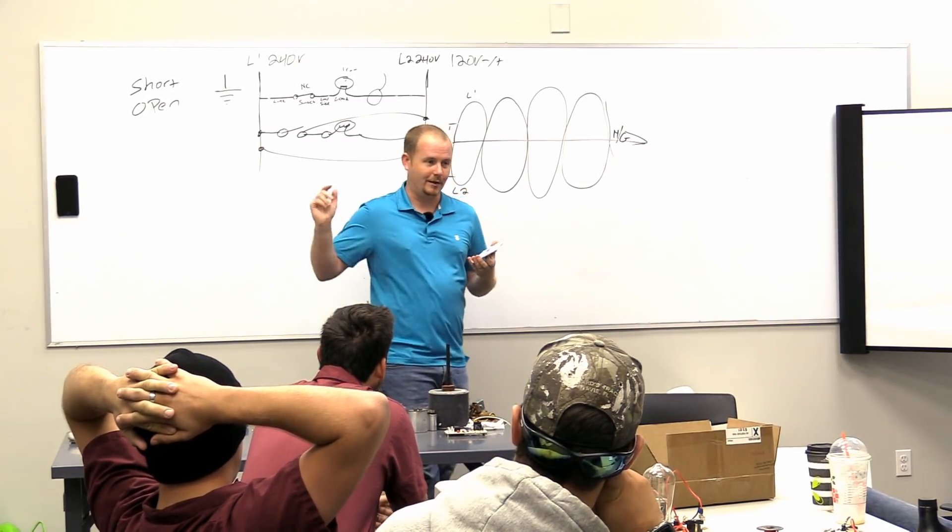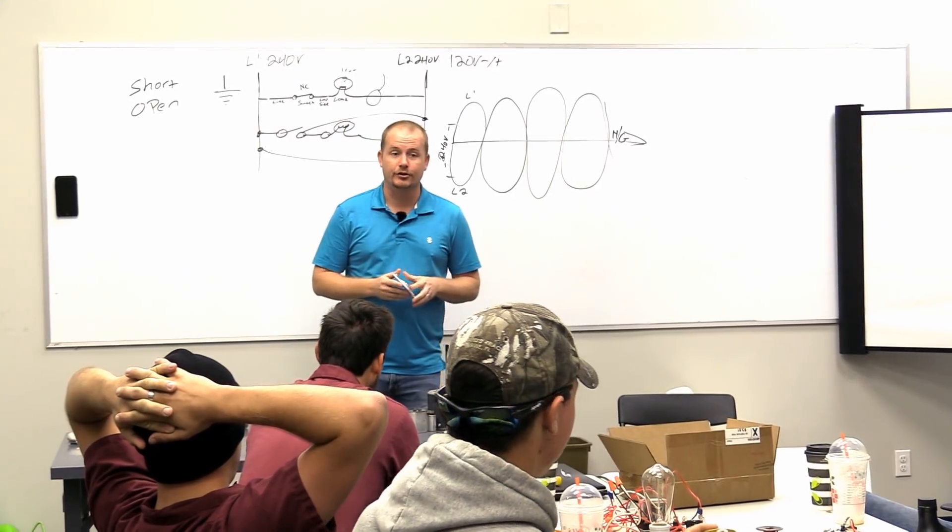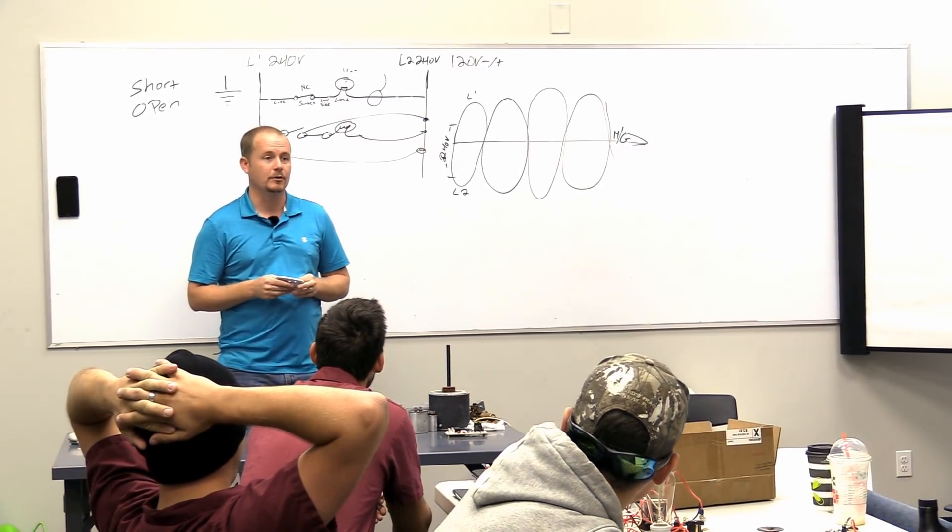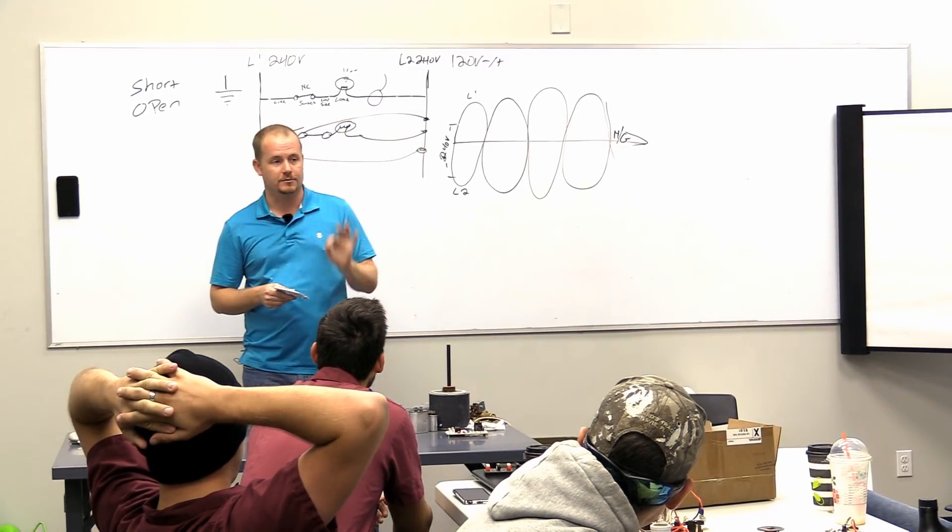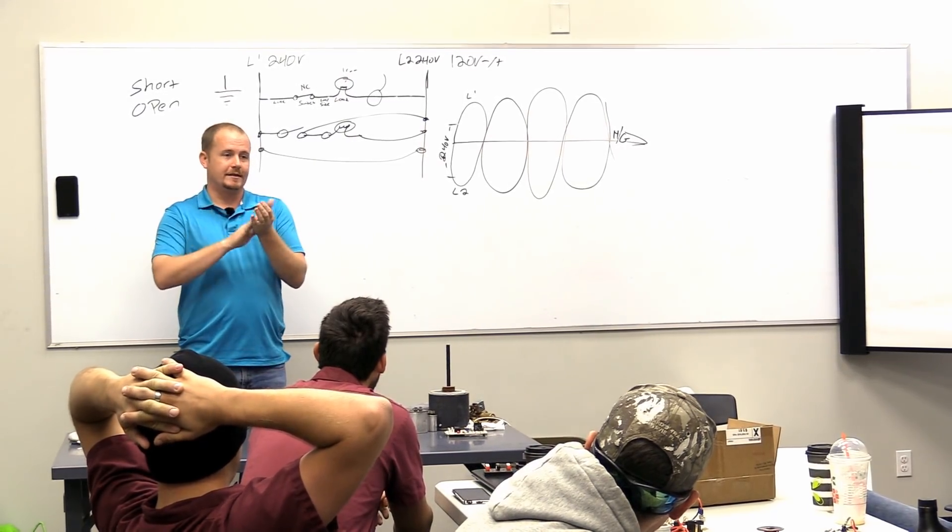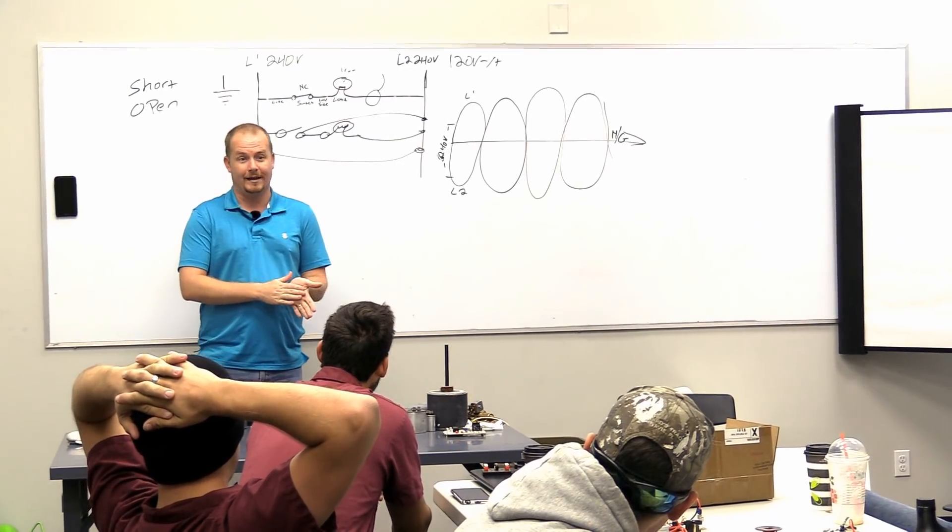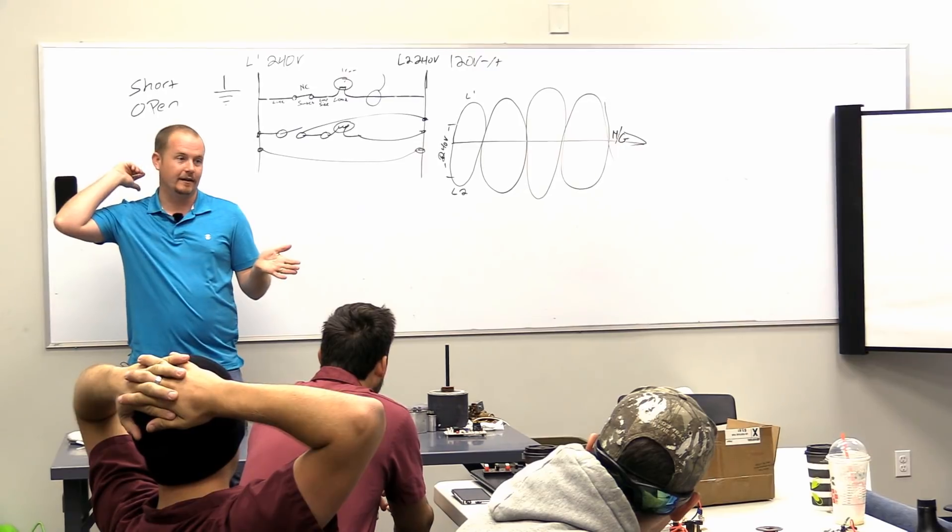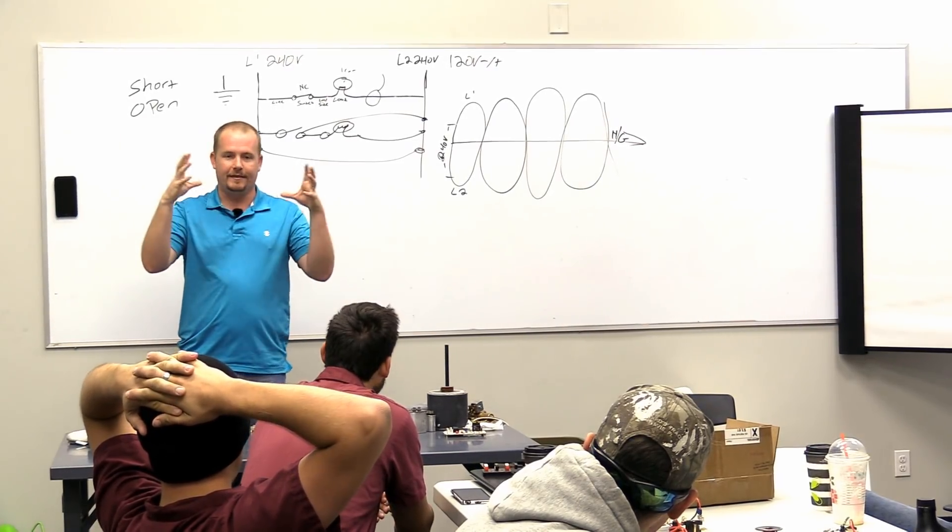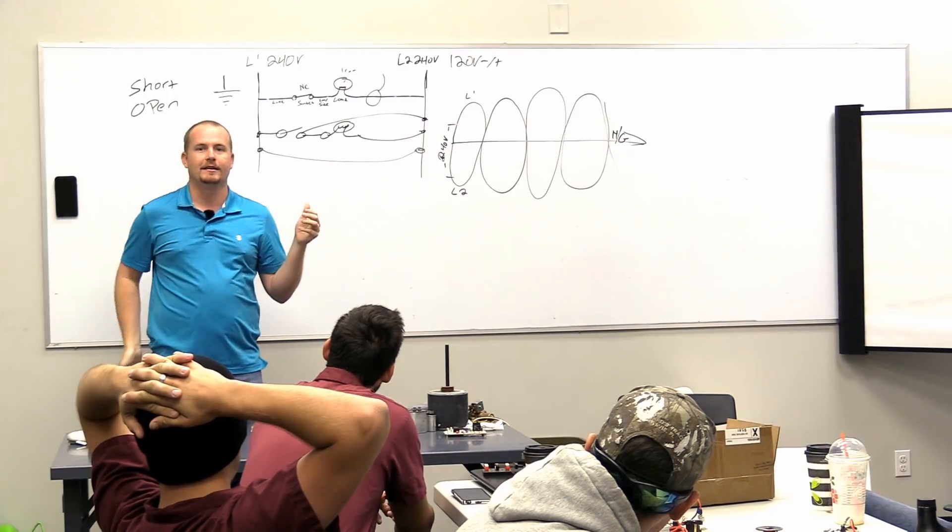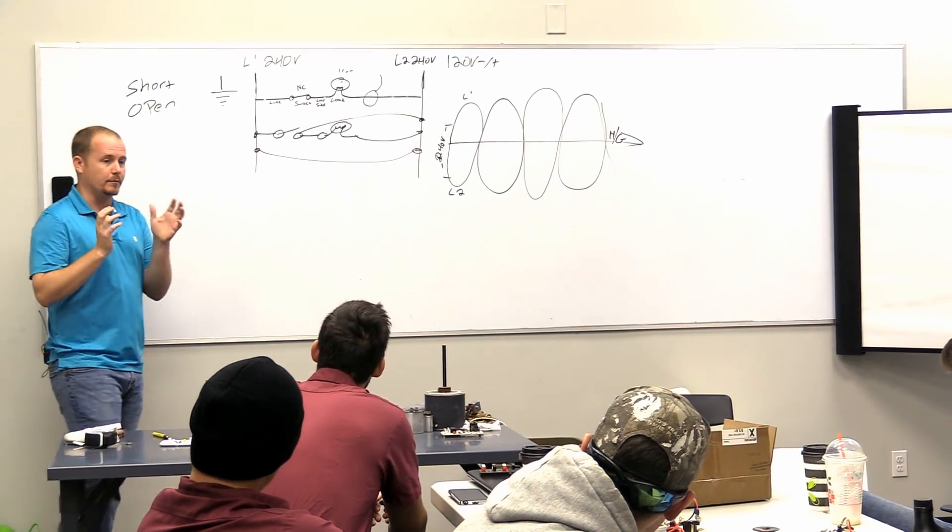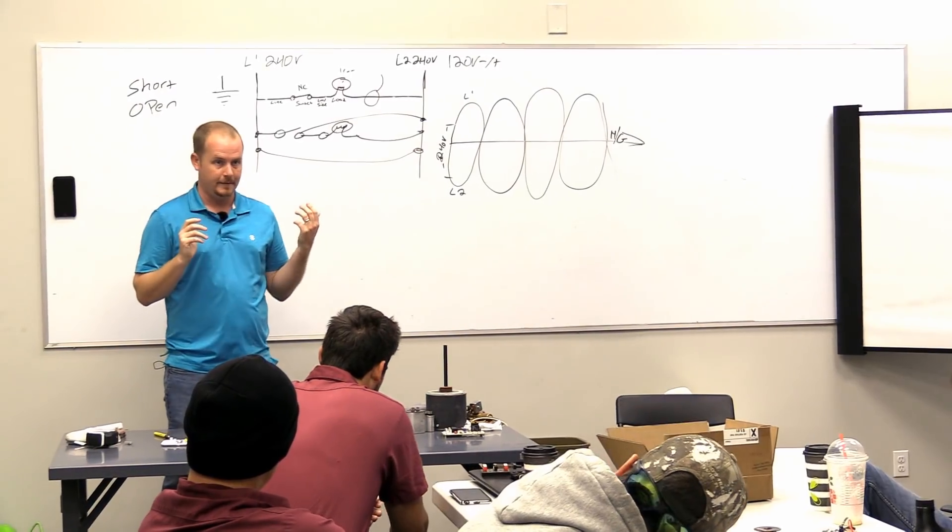Now that's not how you should do that. You shouldn't just walk up and reset breakers. But, just as an aside, what should you do if you walk up to a system that has a tripped breaker? I know that that's what most of you do, but that's not what you should do. You should do a full visual inspection of that piece of equipment before you reset that breaker. Because let's say that it arced out. This has happened where it's a high voltage line that's arced out against the discharge line. But it hasn't blown through it yet. And now you go and you reset it and it finally does the job. It blows through the discharge line and loses all the charge. That's happened. It's rare, but it's happened. Or if it's inside the electrical cabinet and it's a rat's nest and a wire came loose. And now every time you reset that breaker, you're causing a big arc flash. Not only is it not safe for you, it's not good for the equipment. So whenever you find a tripped breaker or a blown fuse, you should always do a visual inspection before you just reset. Always.